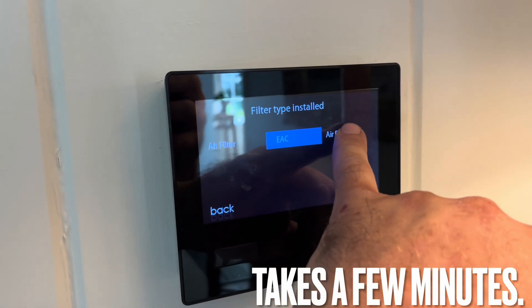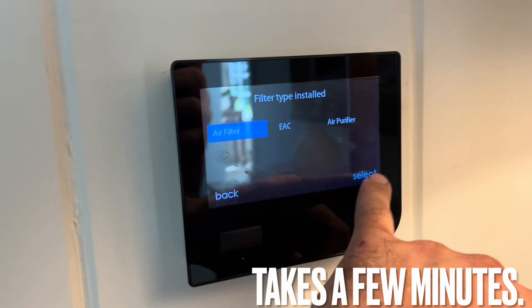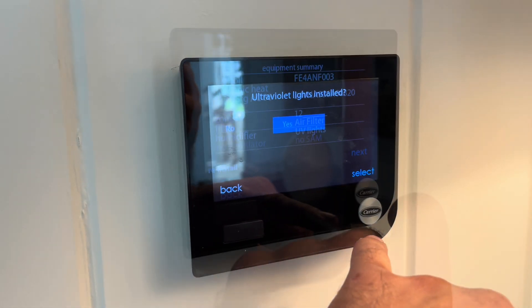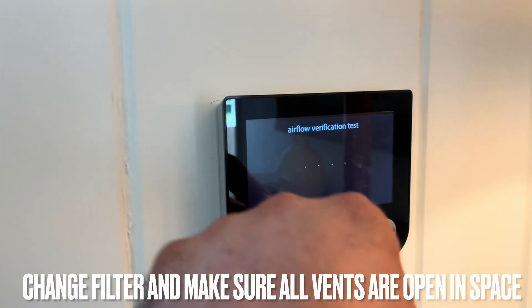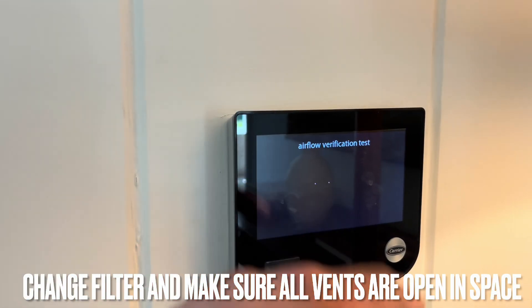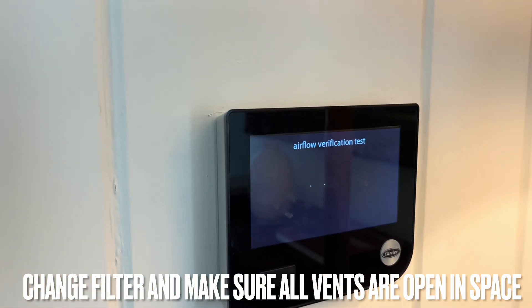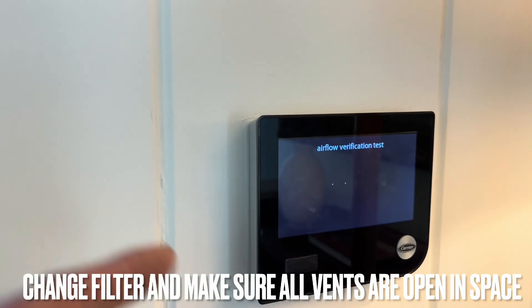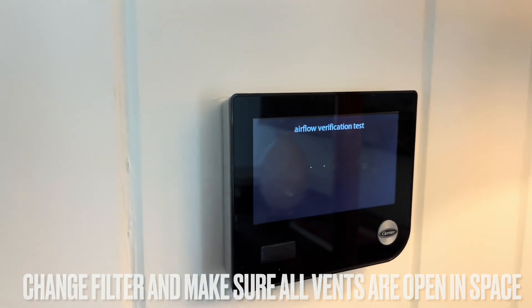It'll ask about the air filter, whether it has an EAC or air purifier — this one has an air filter — select humidifier, yes, etc. Then it'll recalibrate itself once it does the airflow verification test, because it ramps up and down based on static pressure. If it's really dirty or the duct sizing is off, a dirty filter will slow it down — but usually it'll slow down after a filter change.